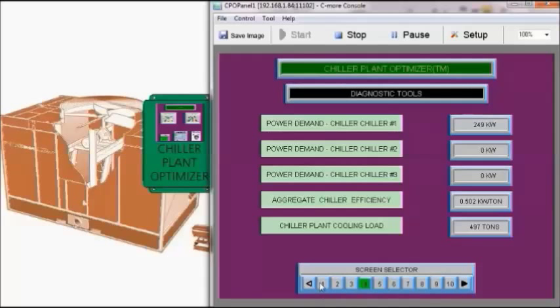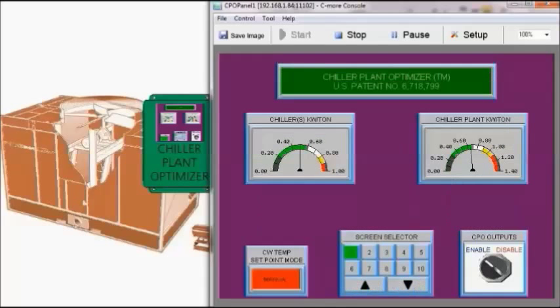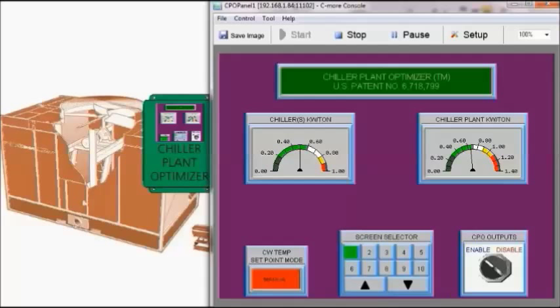We can look at our plant kW per ton and it is about 0.66. This change has nothing to do with the condenser water reset as we haven't changed the condenser water temperature. This is all due to the fact that we're using a variable speed chiller.